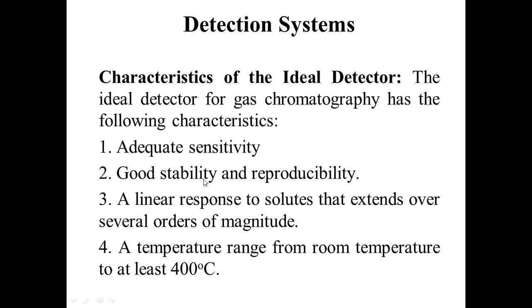We will be raising the temperature up to 400-600 degrees Celsius. So the detector should produce stable and reproducible results. It is very important. Its functioning should be ideal, irrespective of the temperature, irrespective of the sample, irrespective of the conditions we are going to maintain, and even irrespective of the nature of the mobile phase, whether you use hydrogen, helium, krypton, neon, xenon, argon, nitrogen, whatever it is. So stable and reproducible results must be obtained.